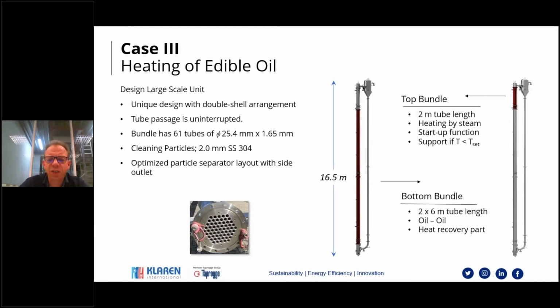I must say it's really a unique unit. Of course, people always say that about their own products, but in this case, I can tell you why we say it's unique. Because we have a design with a double shell arrangement. In fact, we have one uninterrupted tube passage of the oil, so that it will go from bottom completely to the top, but we have heat input from two different sources. At the bottom, we have heat input from the oil coming from another process step. And so the hot oil that I was already talking about, we will cool it down and use it to heat up the incoming oil.